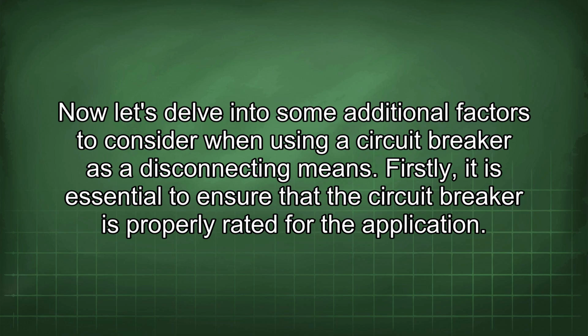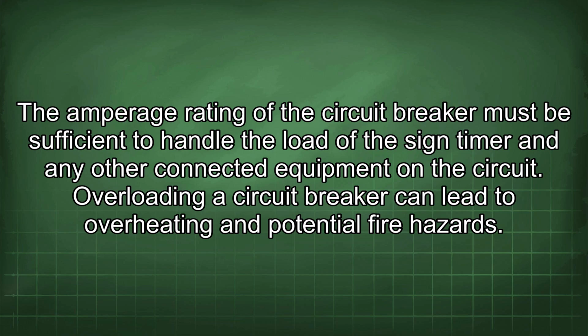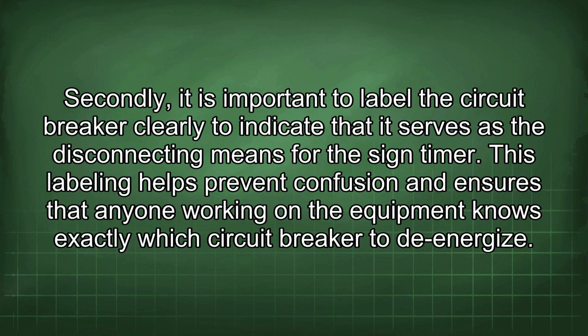Now let's delve into some additional factors to consider when using a circuit breaker as a disconnecting means. Firstly, it is essential to ensure that the circuit breaker is properly rated for the application. The amperage rating of the circuit breaker must be sufficient to handle the load of the sign timer and any other connected equipment on the circuit. Overloading a circuit breaker can lead to overheating and potential fire hazards. Secondly, it is important to label the circuit breaker clearly to indicate that it serves as the disconnecting means for the sign timer.